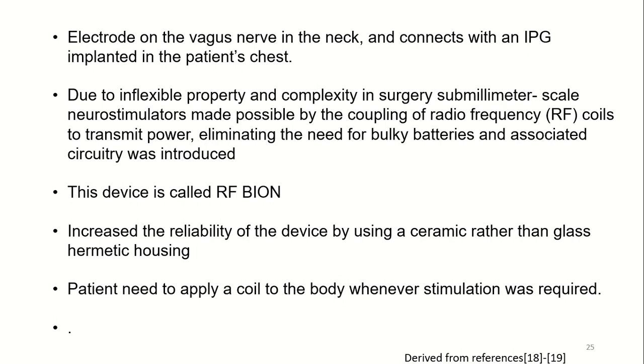Conventional leads have delicate silicone rubber and thin wire construction that must tolerate constant flexing, particularly in the neck. To obtain the degree of reliability expected or necessary for implantable medical devices today, a viable lead may take years of design and surgical method revisions in humans. But these systems have a number of limitations that have long been understood. In 1988, Loeb claimed that it would be possible to construct neurostimulators that are millimeter and submillimeter in size using radio frequency coils coupled to transmit power.